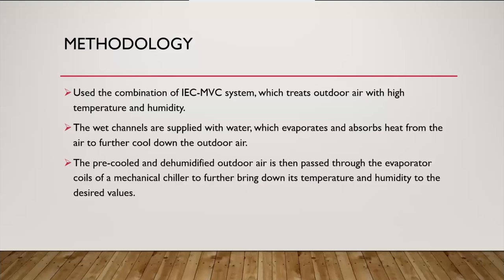For the methodology, it uses the combination of indirect evaporative cooling with the mechanical vapor compression system, which treats the outdoor air with high temperature and humidity. The wet channels are supplied with water which evaporates and absorbs heat from the air to further cool down the outdoor air.